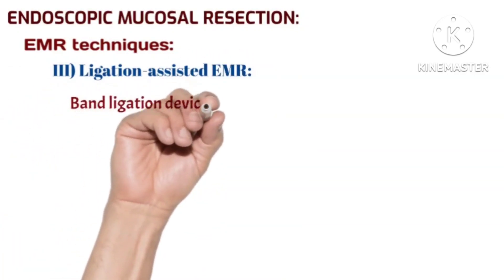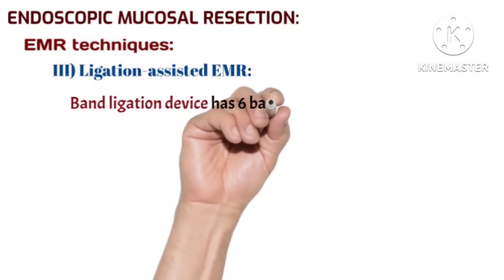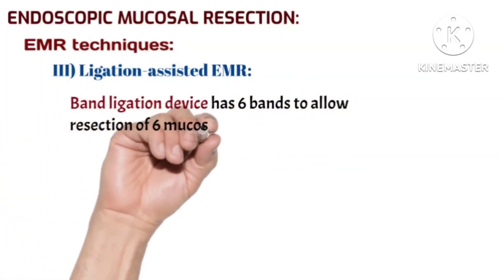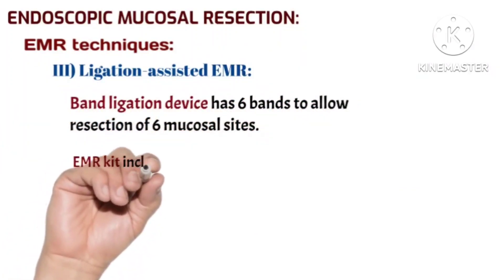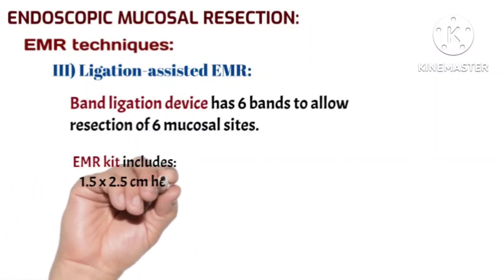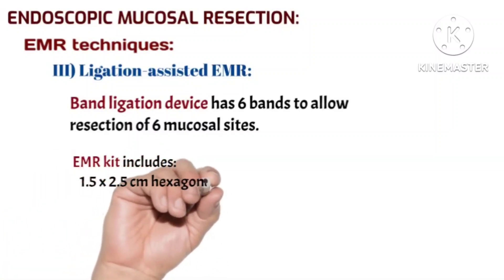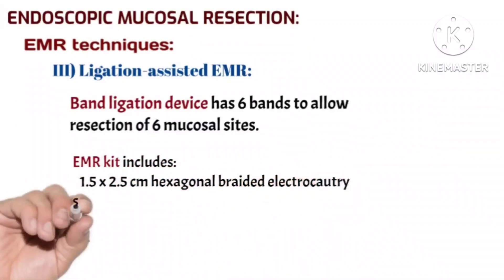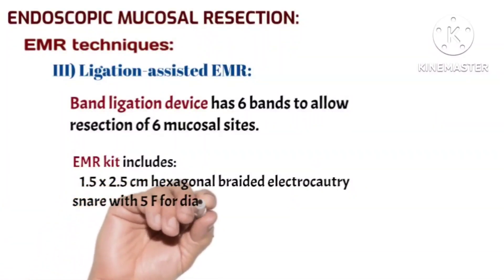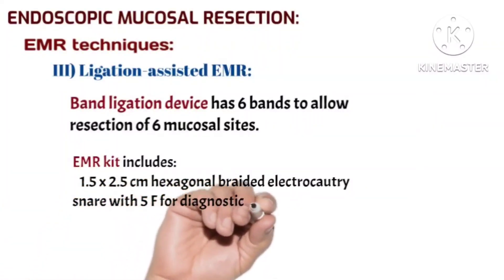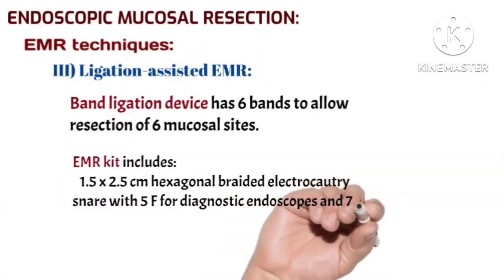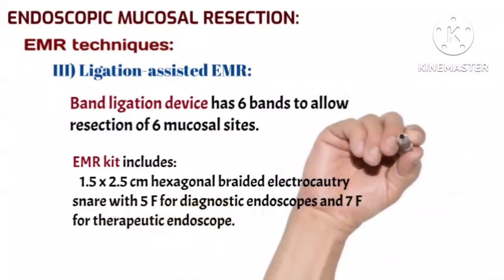The band ligation device has six bands to allow resection of six mucosal sites. The endoscopic mucosal resection kit includes a 1.5 by 2.5 cm hexagonal braided electrocautery snare, with a five-French range for diagnostic endoscopes and a seven-French range for therapeutic endoscopes.